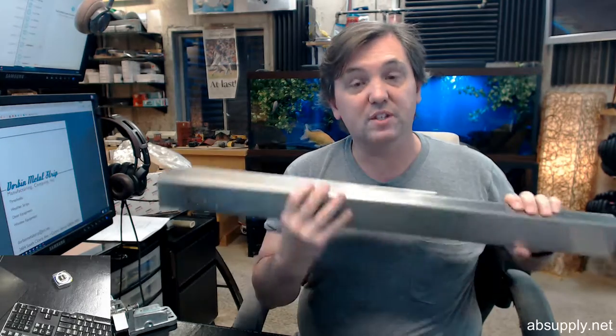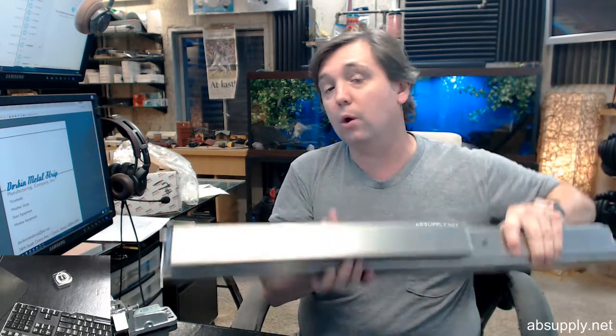So you'll be able to do with the standard, the B device, your 3-foot doors all the way down to 2'4". But then you can do a C device, which is for 25 inch to 30 inch doors, and that's really where the good part of the Dorma device comes in, because you can get down to very small doors. You might have a scenario where you have pairs of doors that lead out to emergency exits on a stairwell. 80-year-old building in Chicago, going to have lots of these tiny little doors. And your options really are to go with a crossbar device that will allow you to trim that bar down, but you might have pairs of 2'4" doors. Well, you can get a modern touchpad style device from Dorma and fit it onto those doors, and that's the key part of the 9000 series device, that you can work with very small doors.